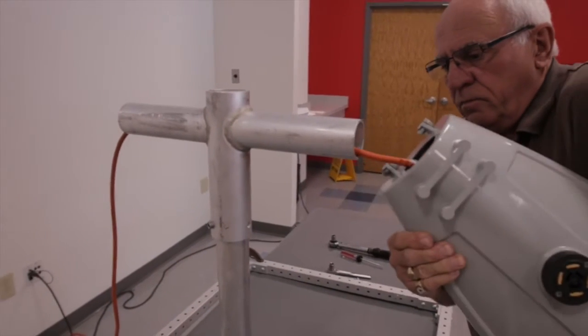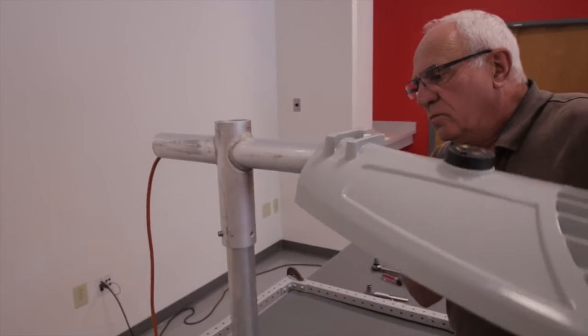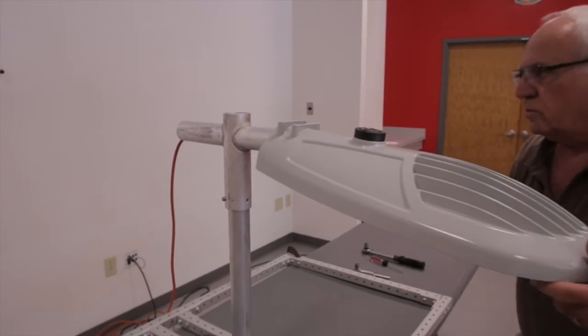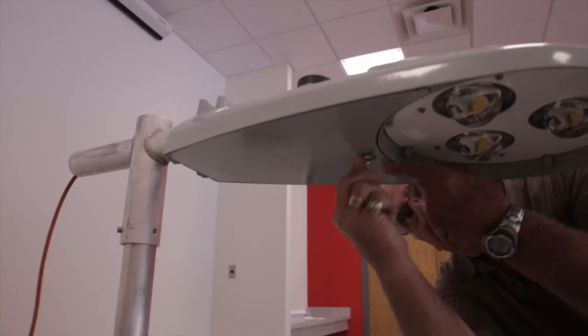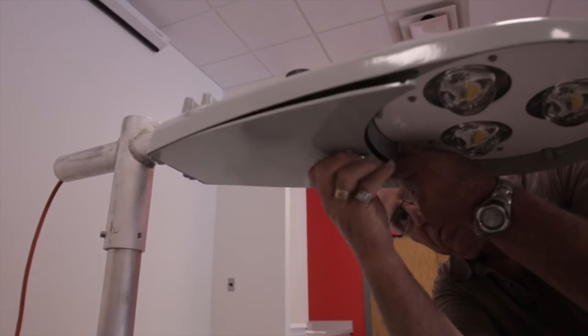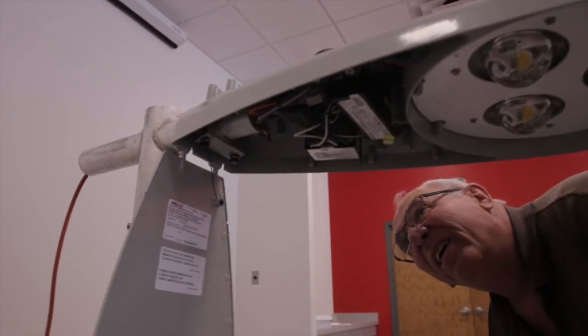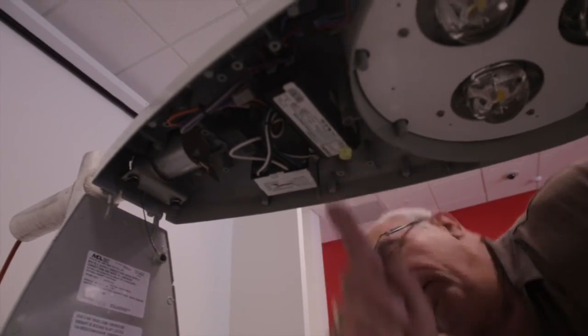Ensure the power has been disconnected, then feed the electrical wires through the opening and lift the luminaire back onto the arm until it stops. Next, loosen the wing screw and open the electrical access door. Check the bubble level to ensure the luminaire is level.